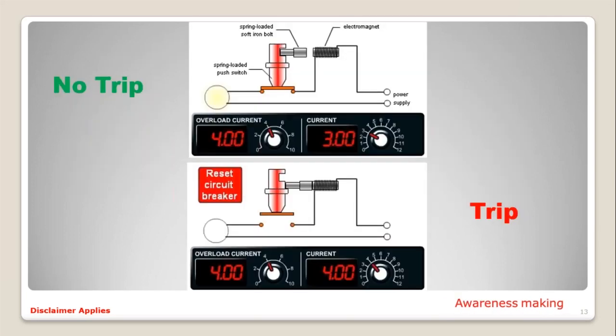So here is a brief explanation of how the circuit breaker works. When you have an inrush of current and it's overloading, the electromagnet will pull the pin that gives you the tripping function for overload. But when you have a short circuit, that's a quick inrush of current that will make the circuit breaker trip. But if there's no earthing to it, it can't see that inrush current, and that is where you will find typical wires that are burning or a big dead short.